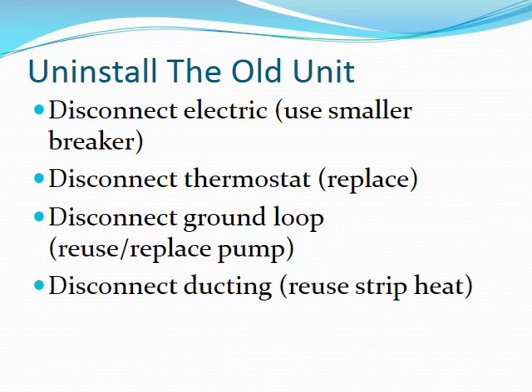Uninstalling the old system was a breeze. I disconnected the electric, the thermostat, the ground loop, and the ducting, and pushed the old system aside so I could make room for the new. When I disconnected the electric, I did discard the breaker because I had to replace it with a smaller one. And I discarded the thermostat, making sure that I recycled it because my old thermostat had mercury in it.